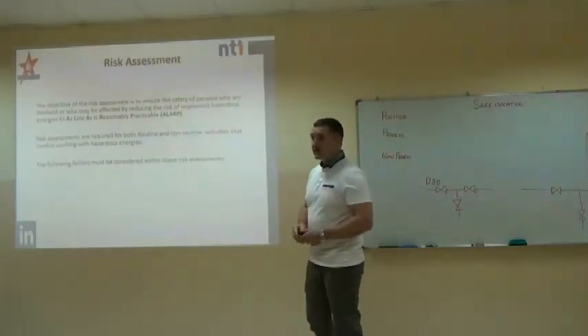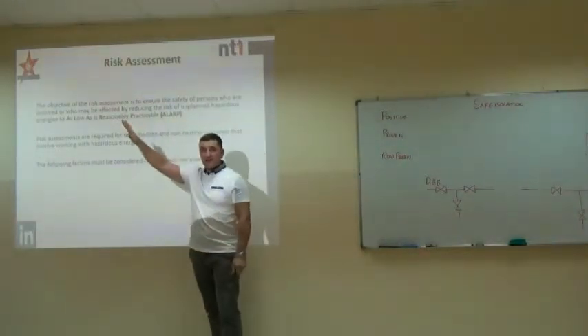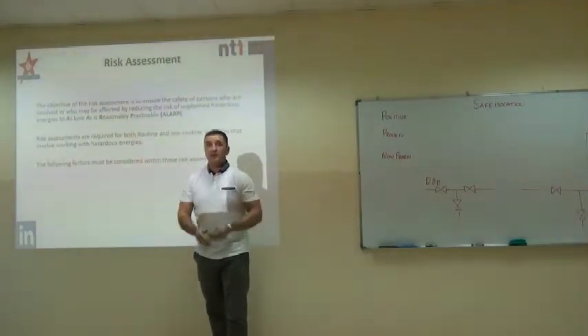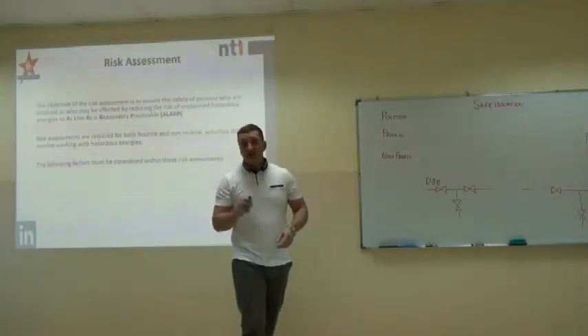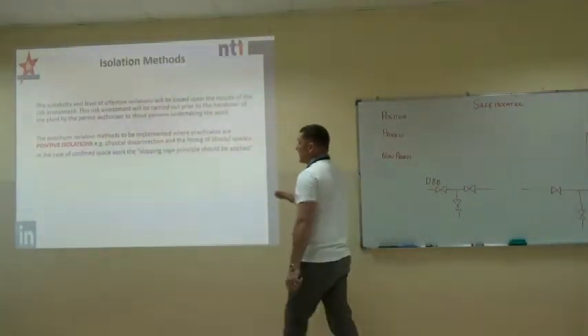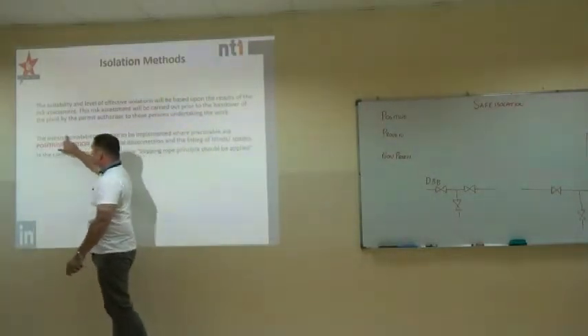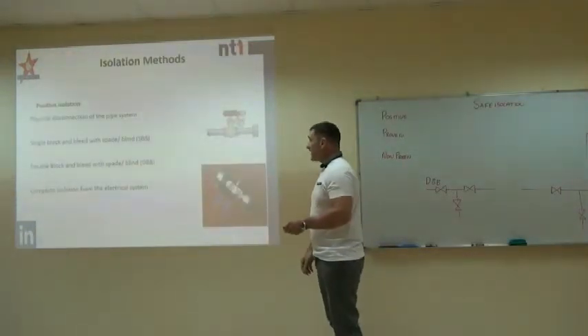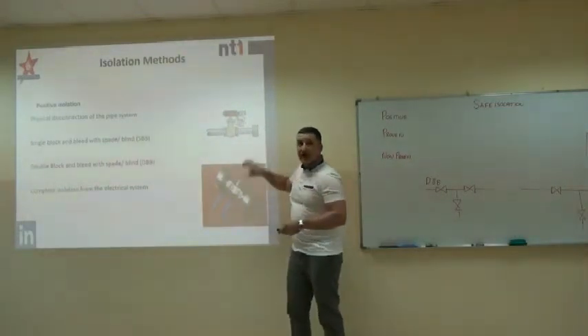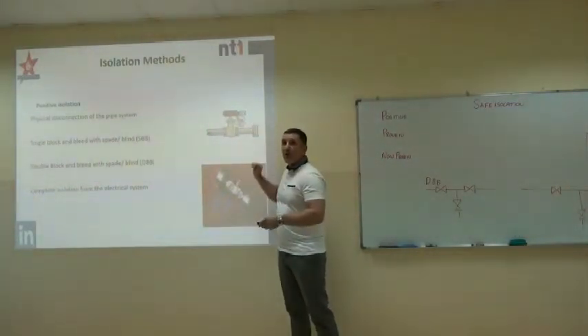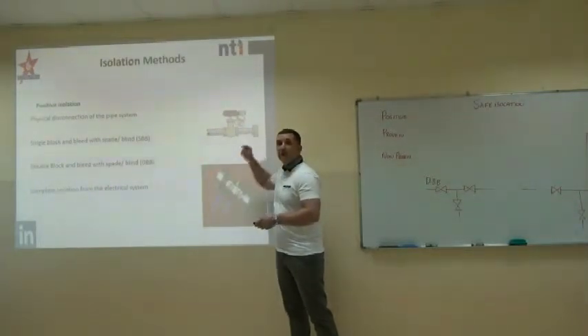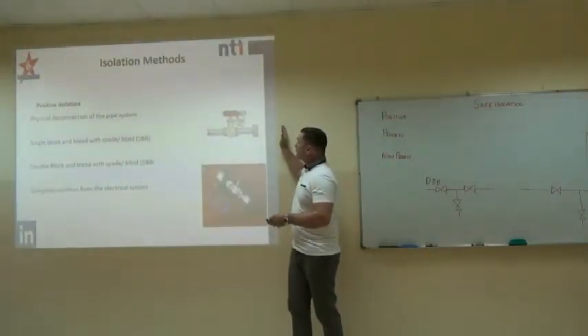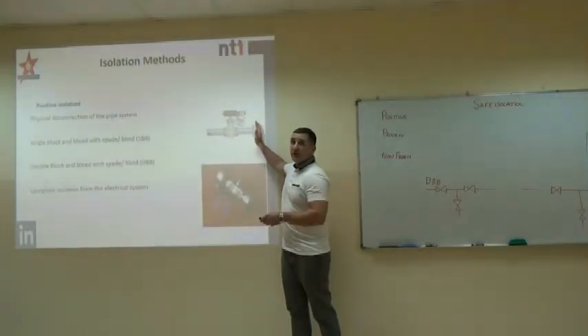We identify the hazardous energies, then we write the risk assessment and reduce the risk to as low as reasonably practicable, and we do that with isolations. There are three types of isolation methodology. The highest is positive isolation — this is a separation of the line and fitting a flange, or we fit a blind or a spade. Blind and spade are the same thing. We never leave any line open in process — we always fit the appropriate blind flange to that pipe.